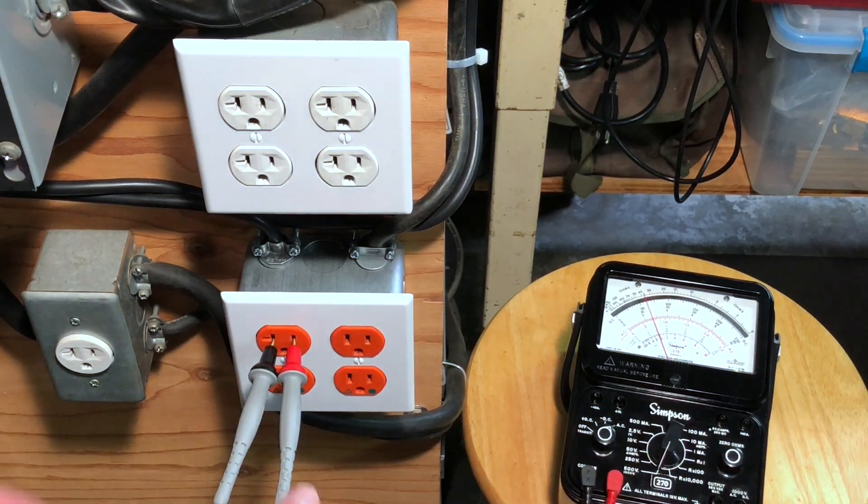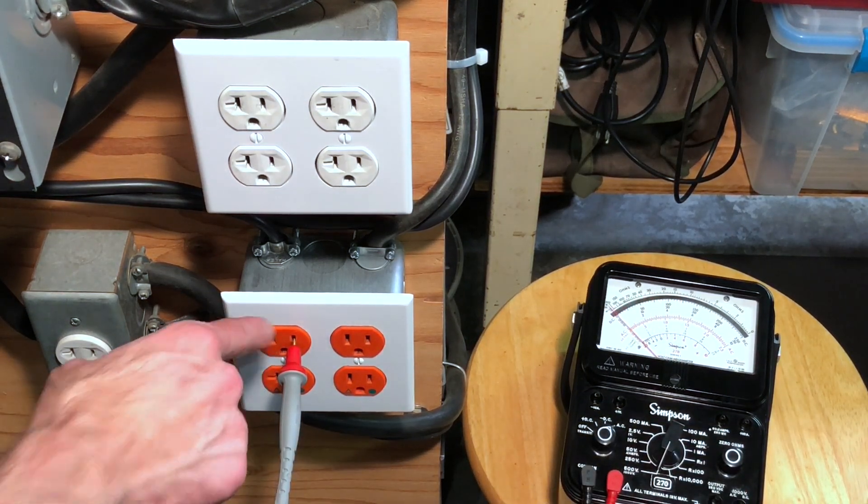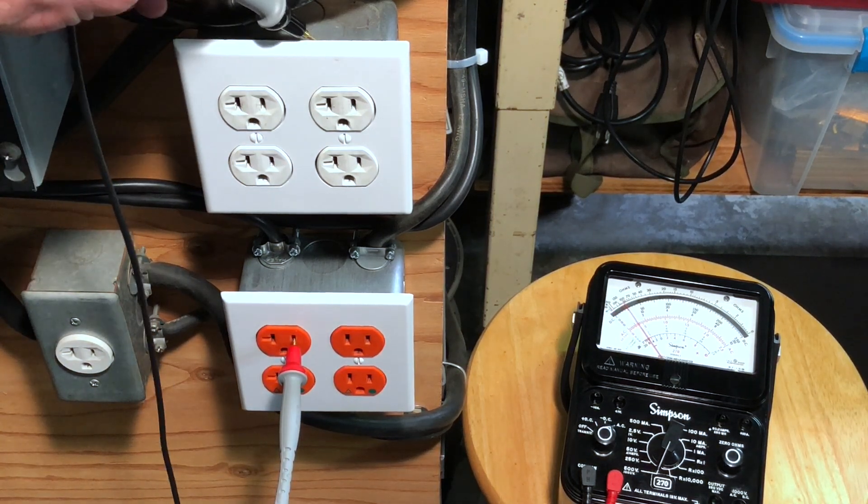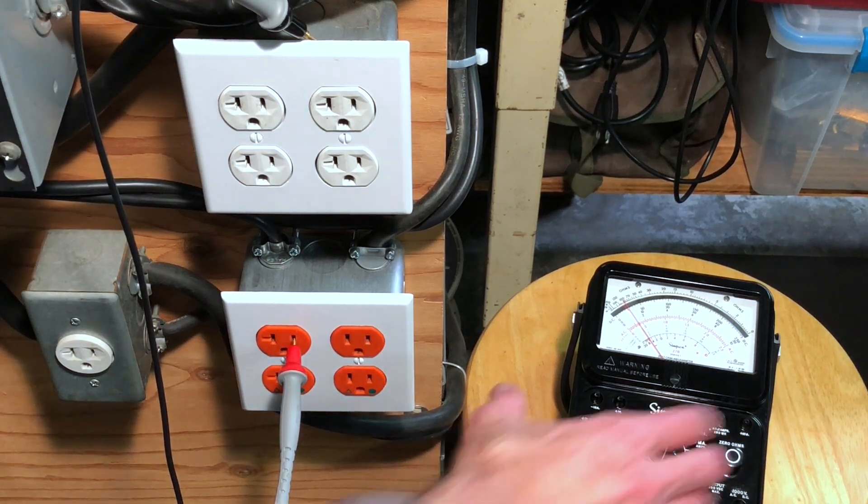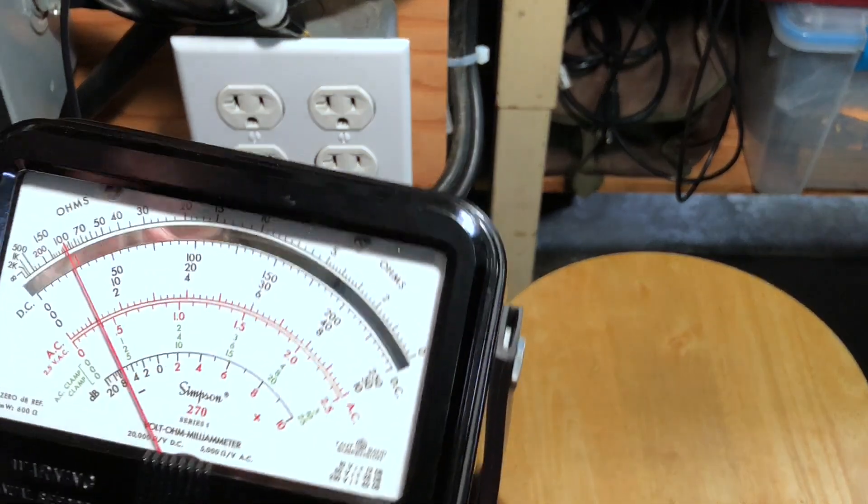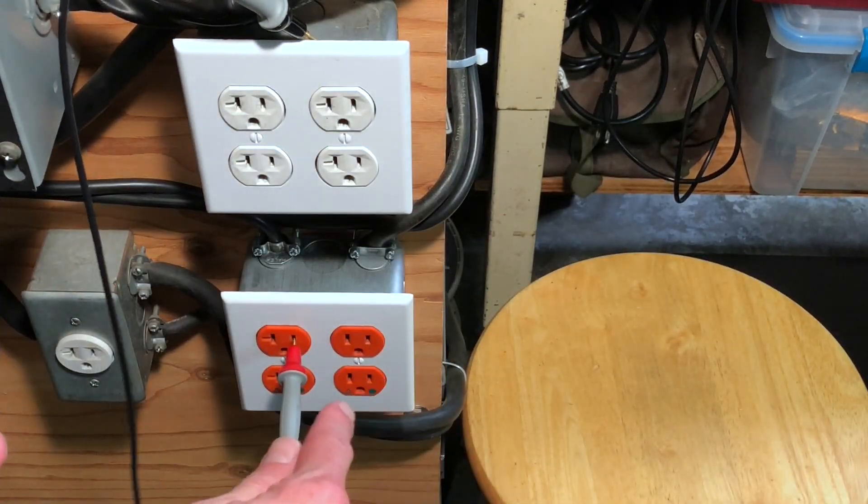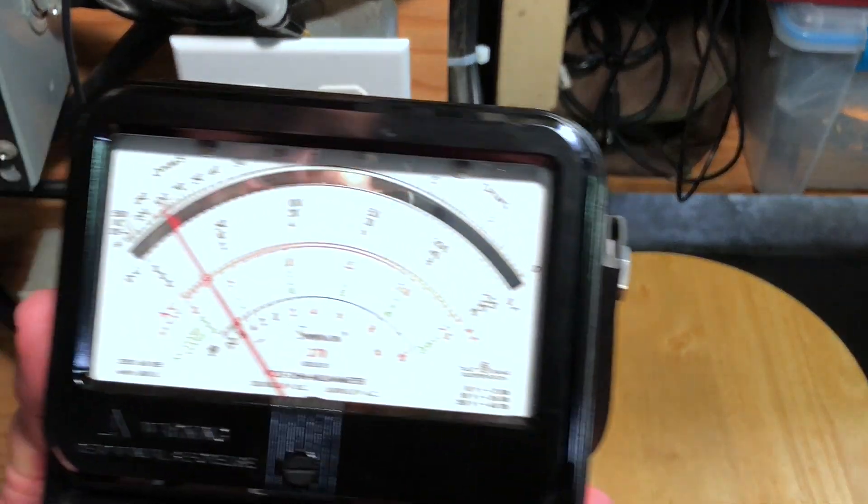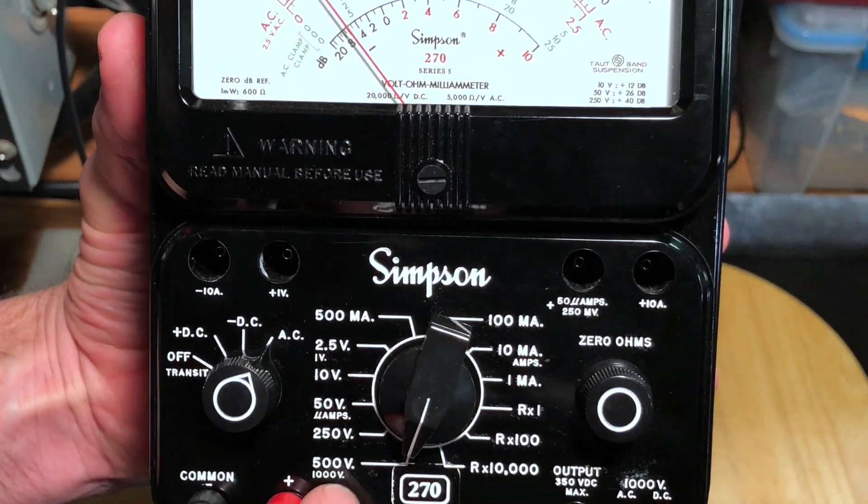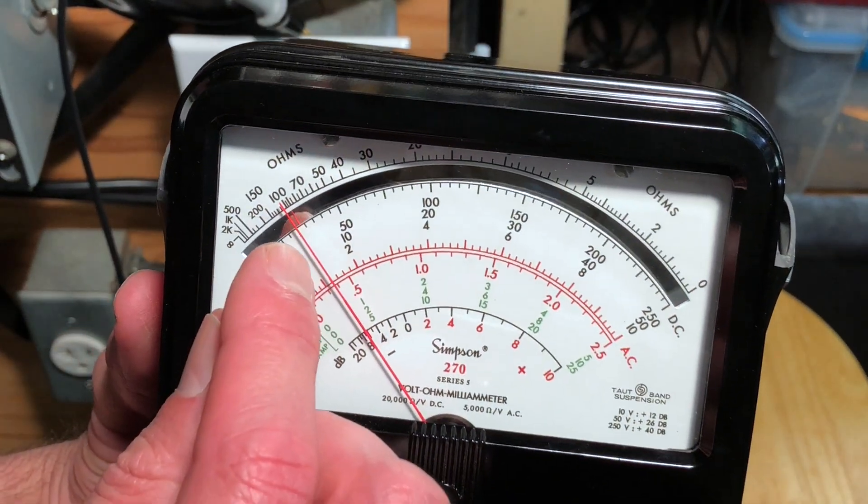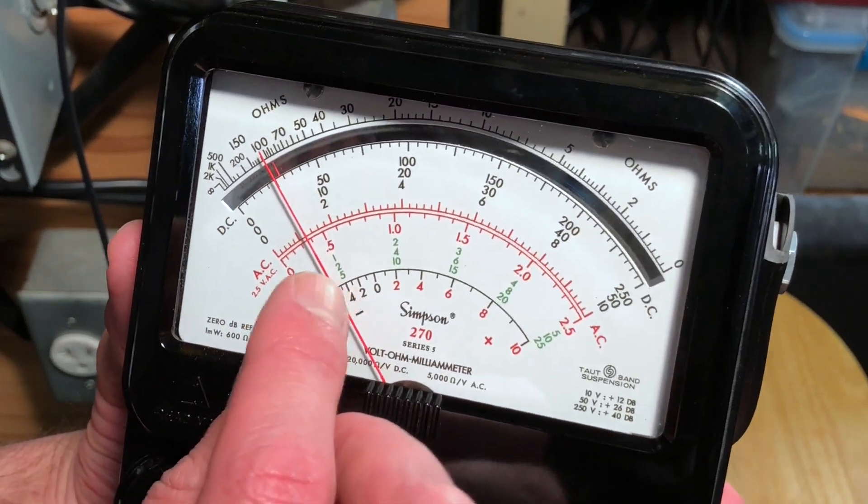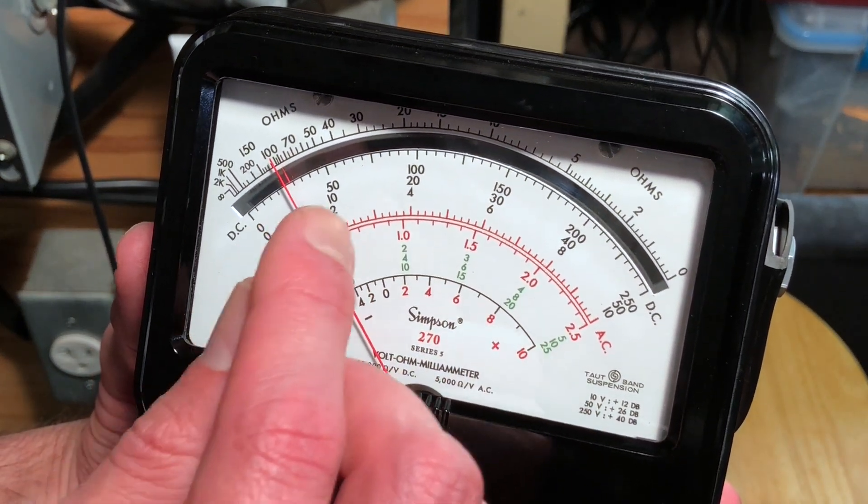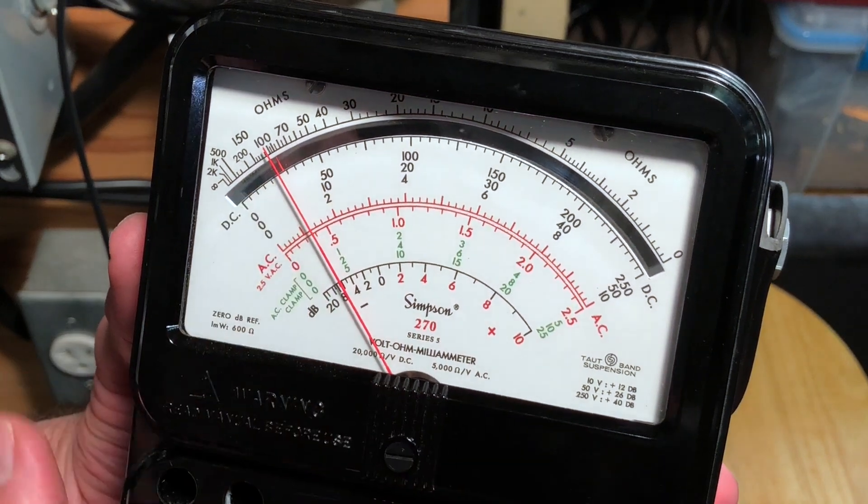Let's go back to 500 volts. I'll leave this on the isolation transformer but go up here to this earth-ground connection. There's a hole right there, you can just poke that in. We do have a reading. One probe is on the isolation transformer, the other probe is up there on earth-ground. You can see right here, 500 volts, and we have a reading down here. So 500 volts, that would be 500, 400, 300, 200, 100, and we're about halfway, so roughly that would be about 50 volts.